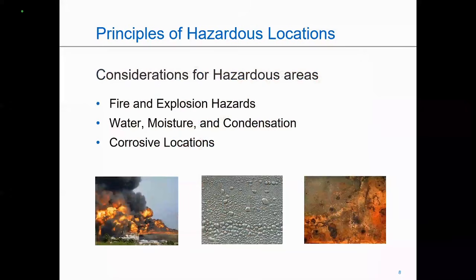Considerations for hazardous areas. Naturally, in a presentation like this, we're going to talk a lot about fire and explosion hazards, but there are some other considerations that we may have. Water, moisture, condensation. When I'm looking at a particular environment, in addition to the NEMA 7 or whatever protection technique I'm using for hazardous location, I also want to be concerned about my environmental protection. Do I need to have a hose down rating, or is it an indoor application? So that's a consideration. Are there areas where moisture can collect in my conduit?